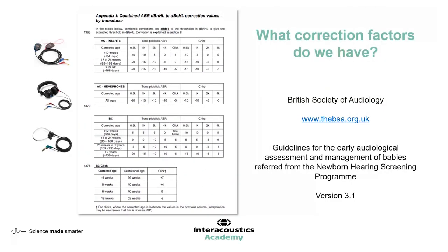One thing to draw attention to is that there are different values for different stimuli — tone pips or bursts, and clicks and chirps. For now it's important to be aware that the chirp category has been based on data using the CE chirp. There are other chirps available, and it is important to be aware that these may perform differently or have different RETSPL values. You'll notice that the document says 'combined correction factors' — let's go on to have a look at what goes into making these values.